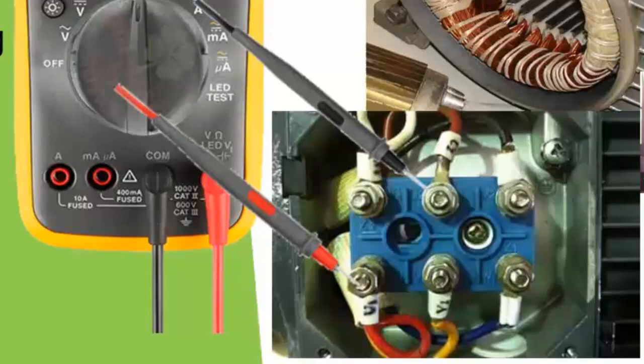Remember we said earlier that these windings, you don't expect them to have connection with one another, which means that as you have removed those shunting bars, if you read continuity between U1 and V1, you will not have any reading to show you open circuit. Then U1 and W1 and V1 and W1, you are not supposed to have any reading at all.